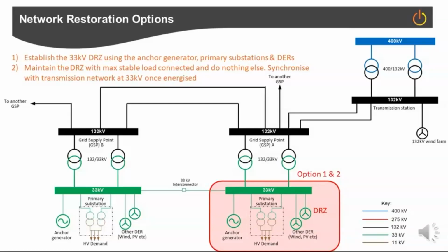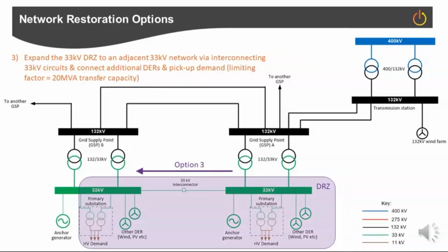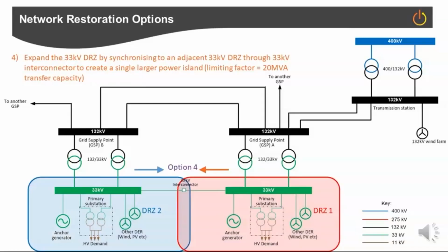The second option is growing that power island and then waiting for a voltage signal from the transmission network, and then synchronizing with that energized transmission system. The third option we've looked at and done some study work on is expanding that power island into another grid supply point area, utilizing the generation and topping up the generation and demand within that power island to grow the overall power island. These are all evolutions of a theme. This is about creating two smaller power islands and then synchronizing them, utilizing the interconnector between those at 33 kV level.